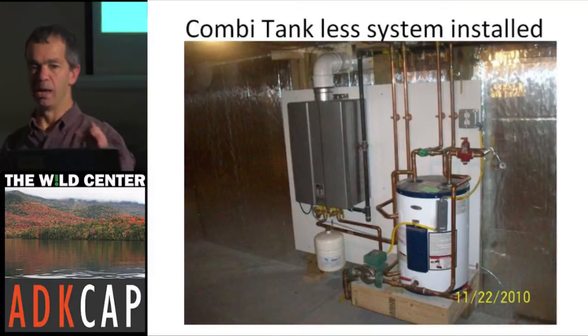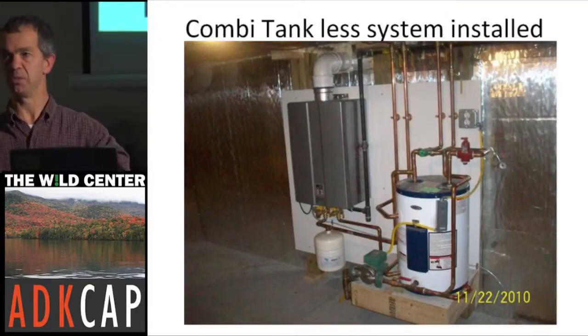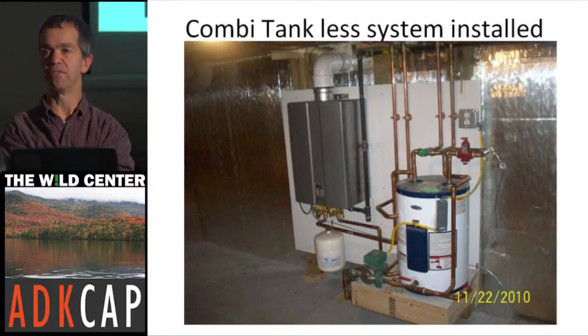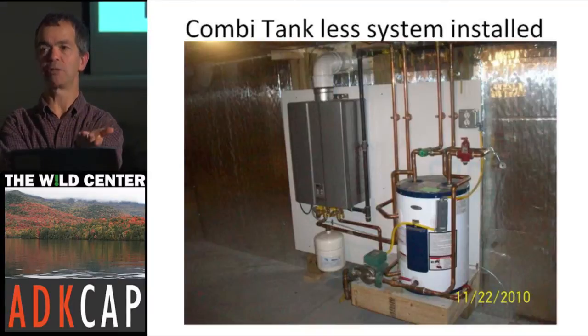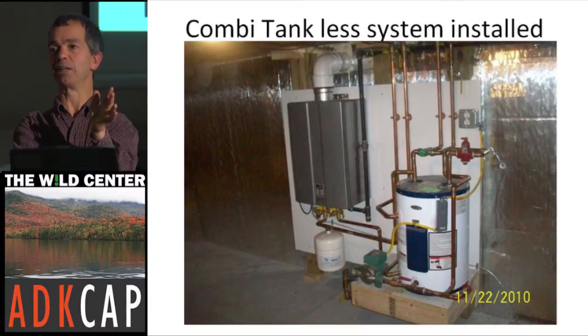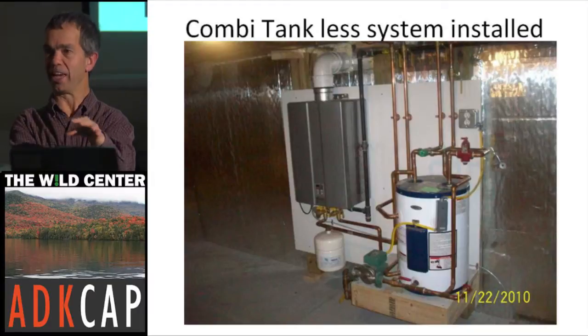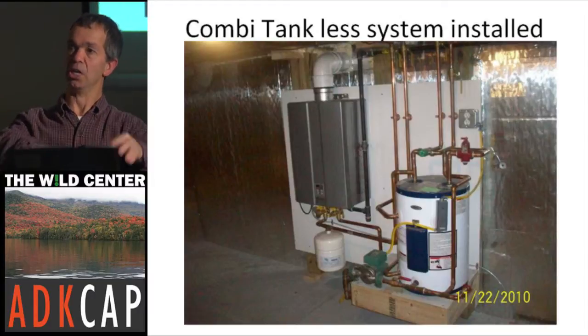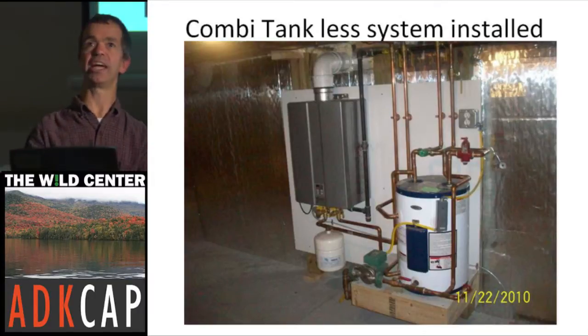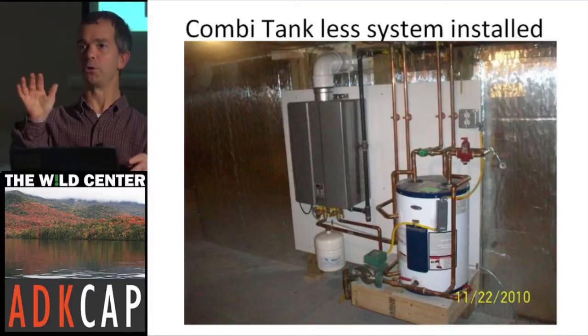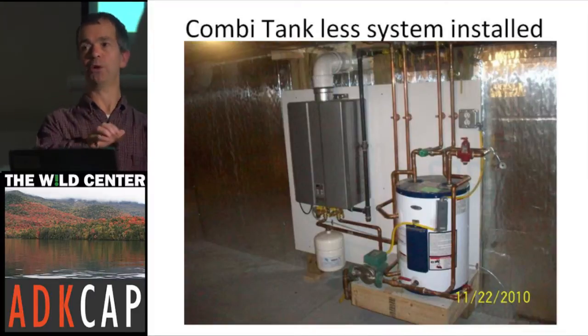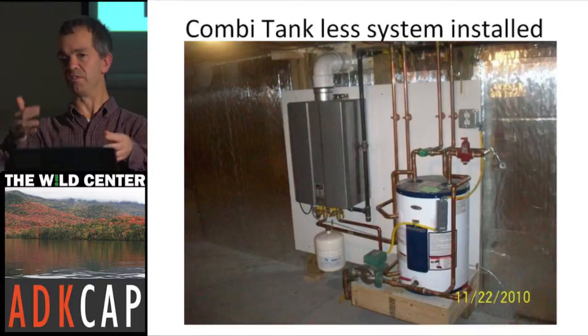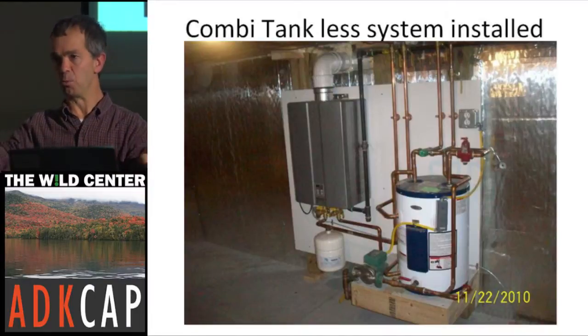So we used the tankless system and added a buffer tank just to be safe. The little buffer tank is an electric tank, but we don't connect the electricity—we just use it as a device for storage. This is for the day when three showers are taken in a row, it's 10 below zero, the furnace is running, the fan coil is running, and somebody's washing dishes.